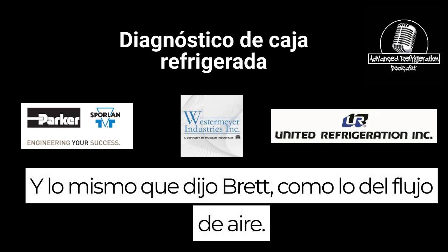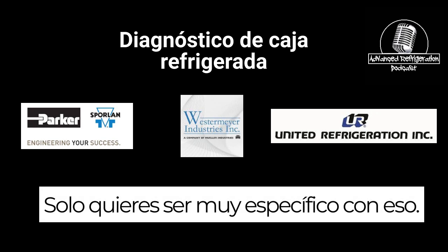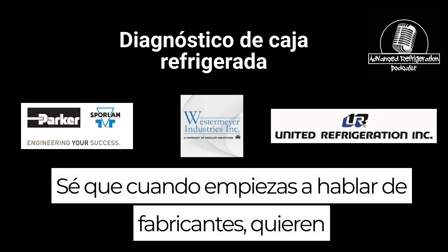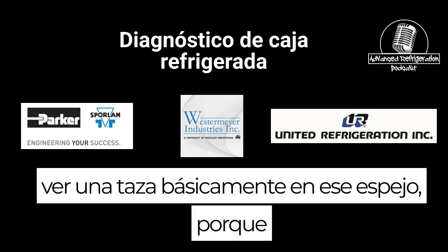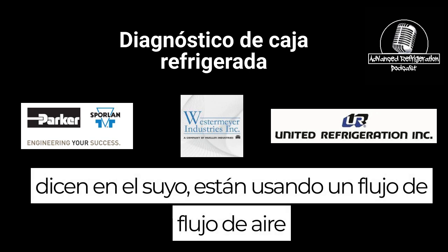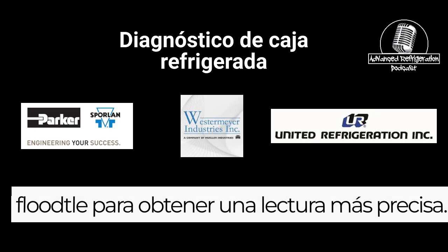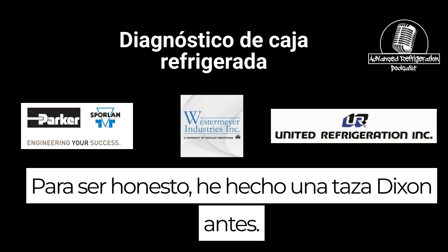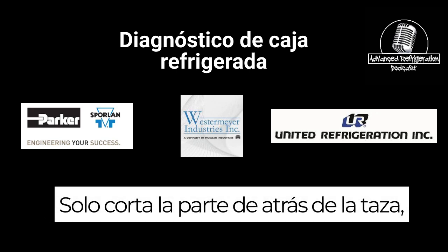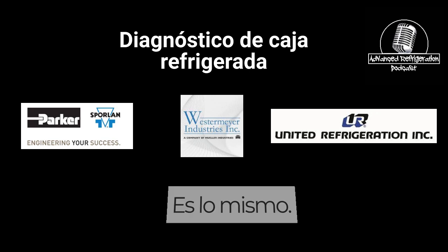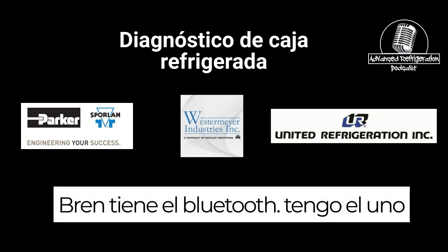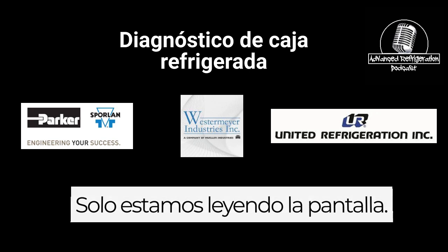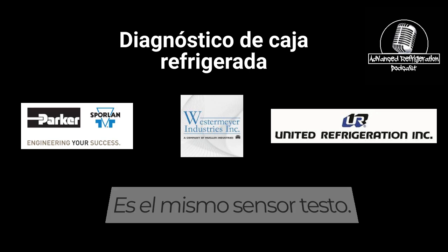And same thing like Brett said with the airflow stuff. You just want to be real specific with that. When you start talking to manufacturers, they want to see a cup basically on that meter, because they say on theirs they're using an airflow funnel base to get a more accurate reading. To be honest, I made one out of a Dixie cup before, just cut the back of the cup out and shove the Testo air meter in there. Brent has the Bluetooth one, I have the one where it just reads on the screen. It's the same sensor, and Testo makes a great airflow meter.